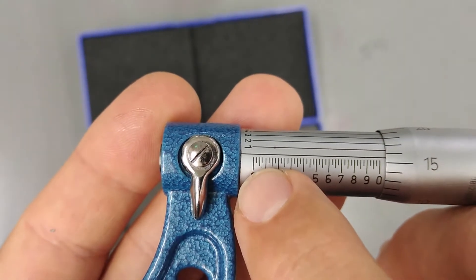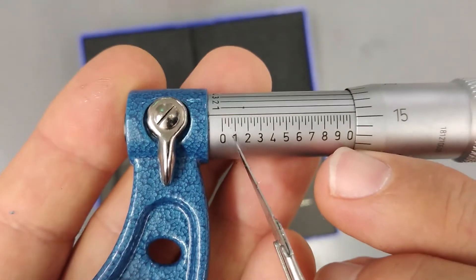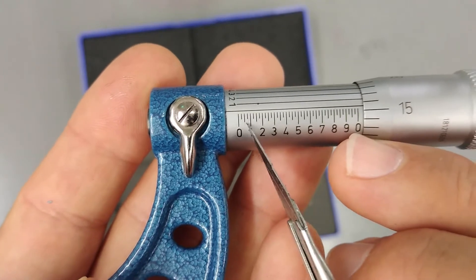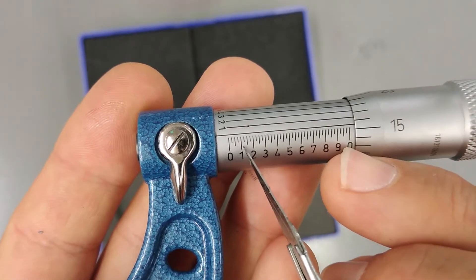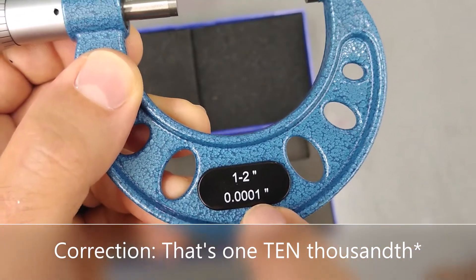Each tenth of an inch gets further divided into four equal parts. Each one of those four equal parts is equivalent to 25 thousandths of an inch — because if one tenth of an inch equals 100 thousandths, and you divide that by four, you get 25 thousandths, 50 thousandths, 75 thousandths, 100 thousandths, bringing you to one tenth of an inch. If a measurement falls somewhere between those marks, that's where this instrument's precision comes in — it can give you a reading up to one ten-thousandth of an inch.